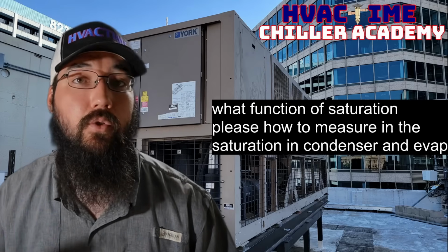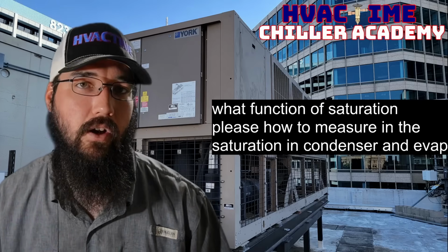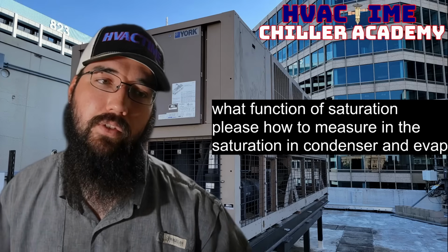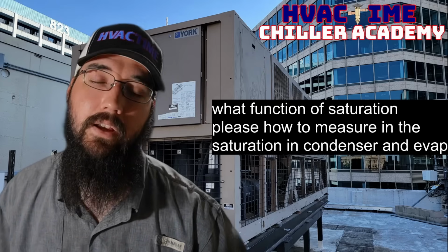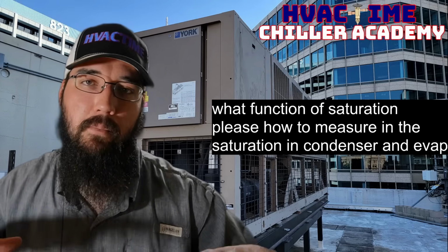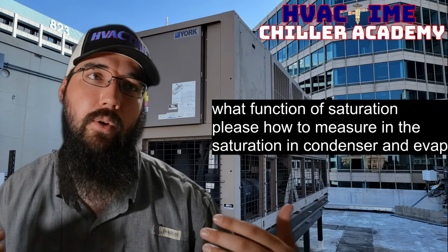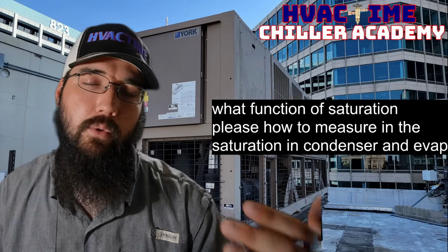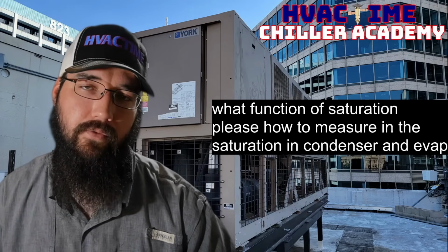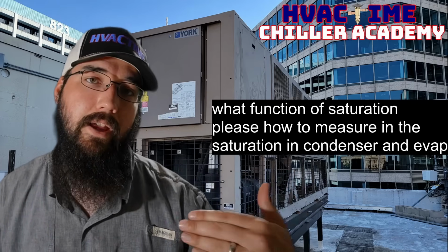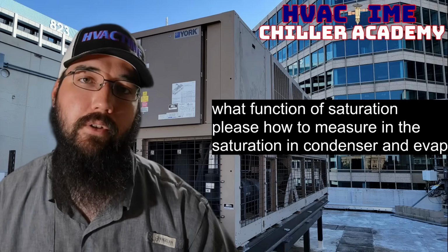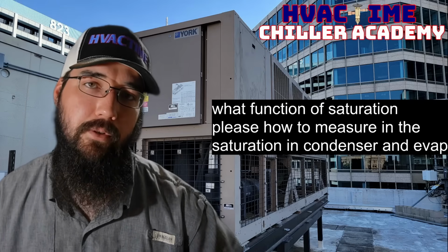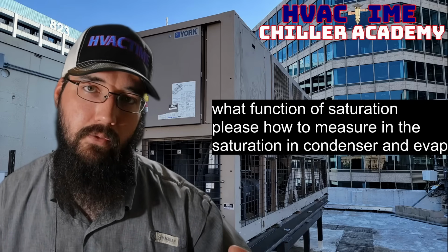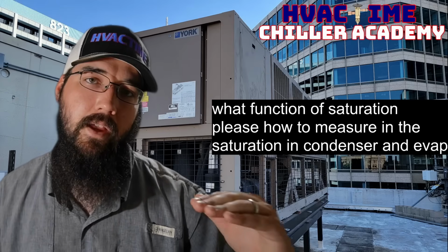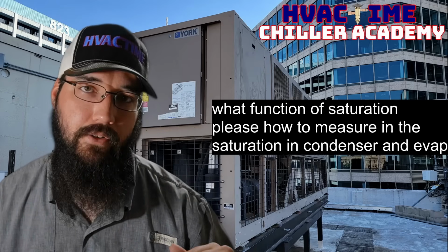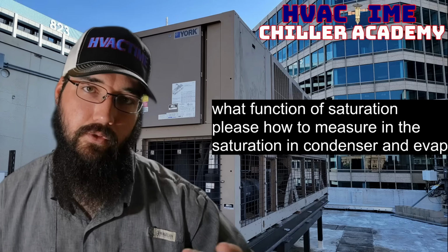And that temperature, we can use it for a lot of things. One, we can use it to determine how well we're transferring heat. We can use it to see where we need to be to move heat, like how much we need to lower the pressure. So if we want a leaving water temperature of 45 degrees on the evaporator, and we have a chiller that uses a 3-degree approach, what that would mean is that with 3 degrees of approach and we want 45 degrees leaving, we need the refrigerant saturation at 42 to achieve those numbers.